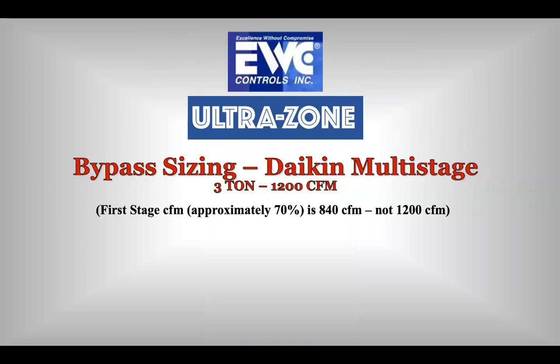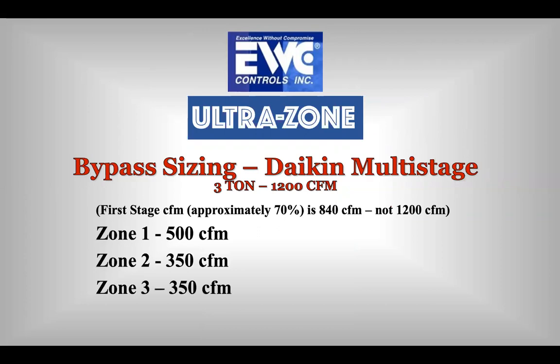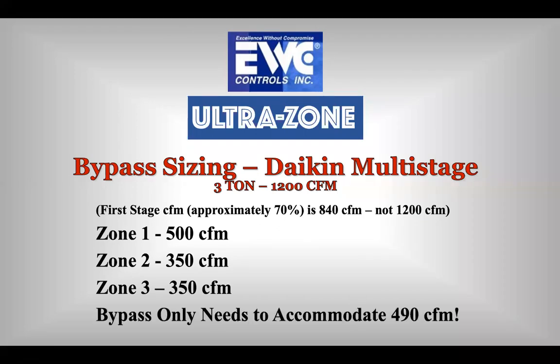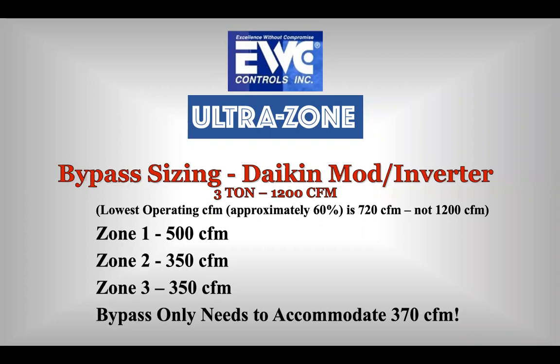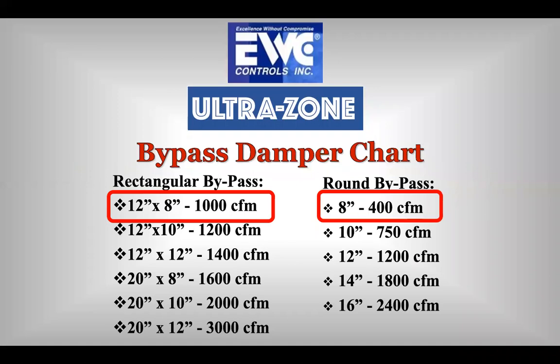If we look at the multi-stage, in this particular case, now we're looking at our smallest zone, one of those 350s. We subtract 350 from 840, not 1200. Drastically reduces us from 850 in a single stage operation down to 490. In the mod inverter, which takes us a little bit lower, 60%, I'm taking my 350 from 720. I'm down to 370 CFM. In all cases, we've lowered the bypass CFM, minimized a bypass CFM. This means my 8-inch bypass will work in both cases.